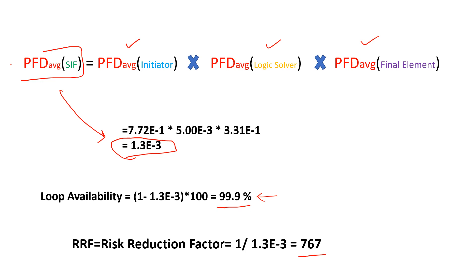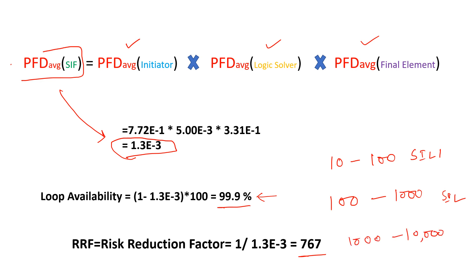The SIL classification based on RRF is: SIL 1 for RRF between 10 and 100; SIL 2 for RRF between 100 and 1000; and SIL 3 for RRF between 1000 and 10,000. Since our loop gives an RRF of 767, it falls in the SIL 2 range from a PFD average perspective.